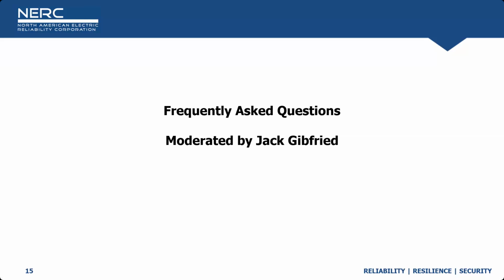That's a question we've definitely received, and it's a great one, particularly because active damping can be separate from injecting oscillatory behavior. Our recommendation largely says: for known oscillation modes, do not inject or cause injection of current, or consumption of current, in an oscillatory manner similar to those modes.